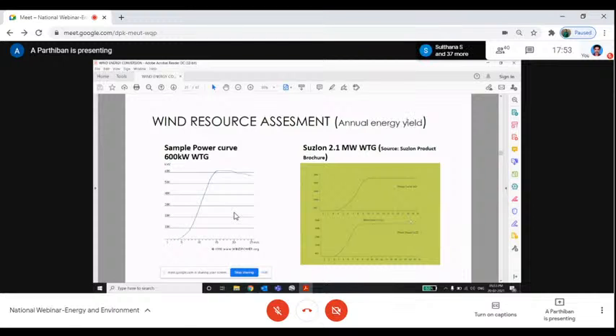For example, the same 2.1 turbine with a rotor dia of S111, the cut-in speed is 3 meter per second. So we can have more output in the S111 type WTG, because at 3 meter per second itself it will start generation, but the S97 will start only at 3.5. At the same time, the rated wind speed will be reached at 10 itself, and the rated capacity of 2.1 will be reached.